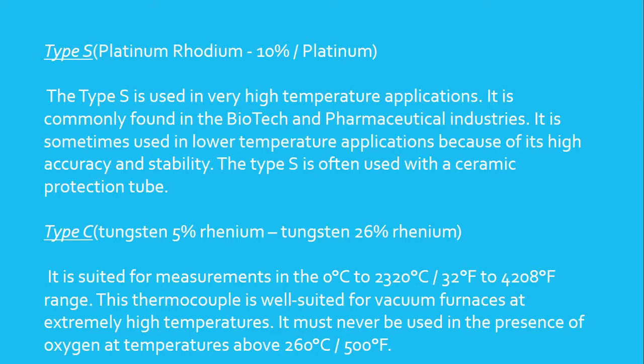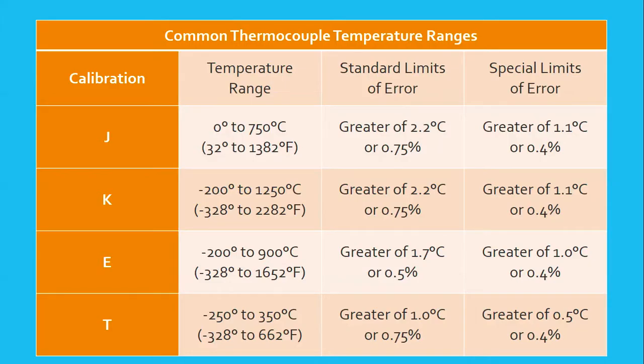Type C is suited for measurements in the 0 degrees Celsius to 2320 degrees Celsius, or 32 degrees Fahrenheit to 4208 degrees Fahrenheit, range. This thermocouple is well suited for vacuum furnaces at extremely high temperatures. It must never be used in the presence of oxygen at temperatures above 260 degrees Celsius or 500 degrees Fahrenheit.